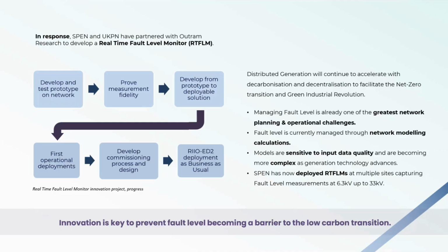So we have lots of offline models of the network where we model all the different assets that are connected to the network, or the generators, or the customers, the load, and through those models we calculate what the fault level is for a given area of the network. But those models are only as good as the quality of the input data, and have to rely on some assumptions in terms of things like feed from the transmission networks, and they're also getting more and more complex as generation technology advances as well, and different technologies are being connected and deployed across the network.